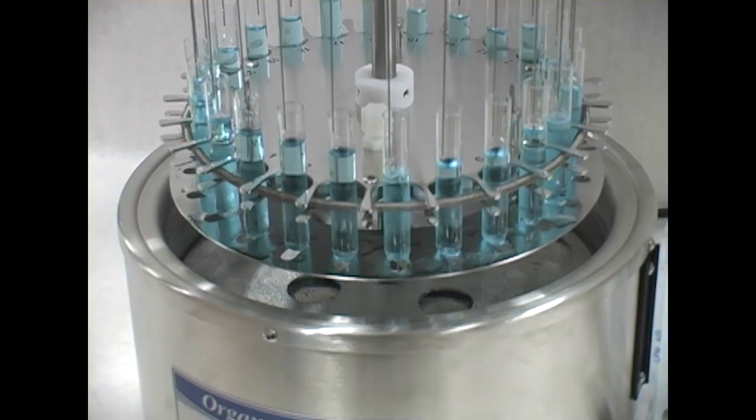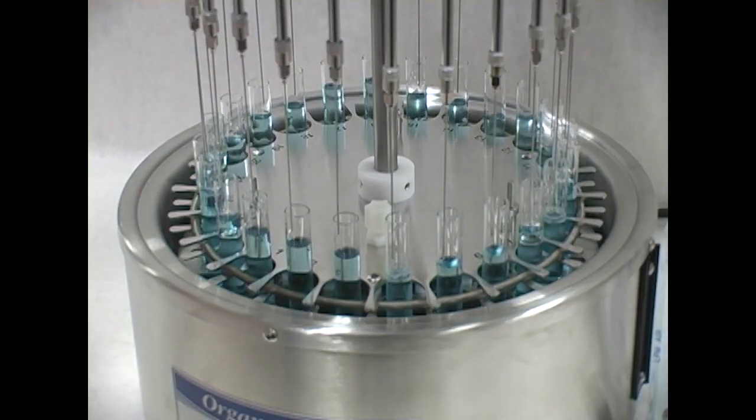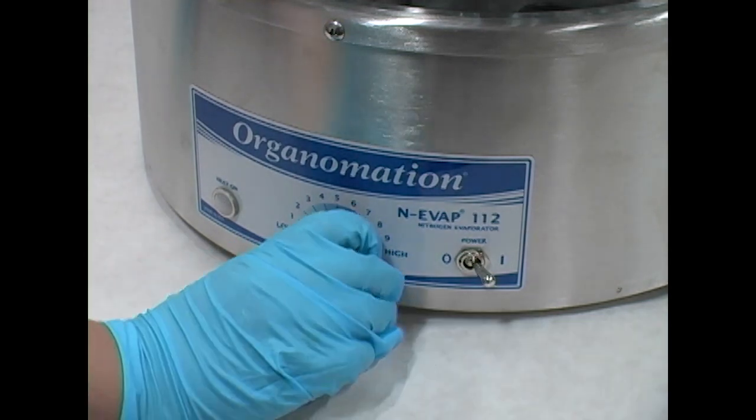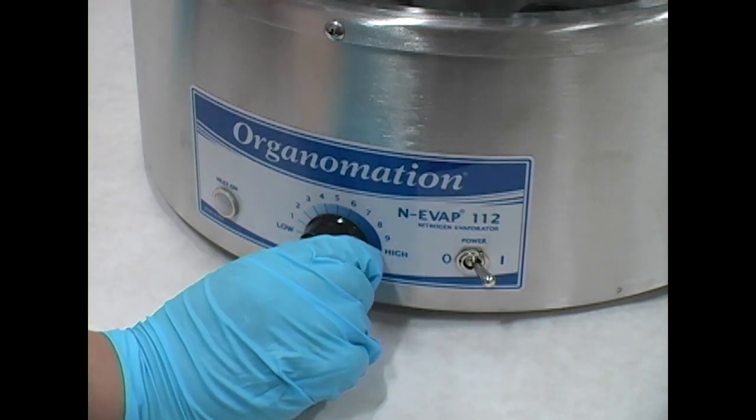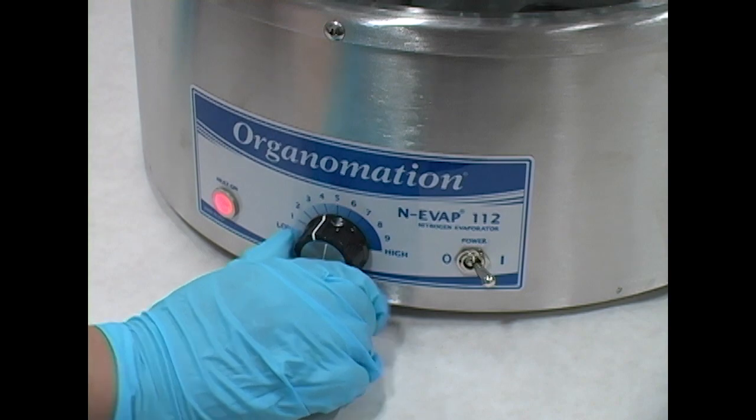Our standard N-EVAP comes with a water bath which provides reliable uniform heat, controlled by a simple mechanical thermostat. These baths are known for their longevity and are capable of daily use for many years.